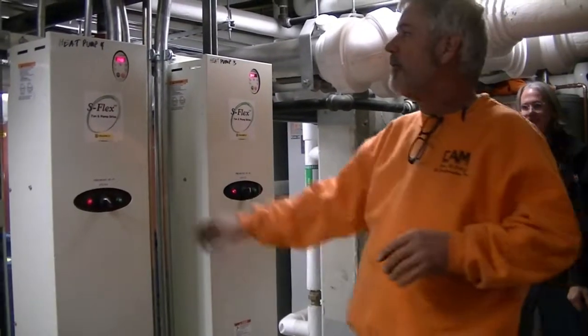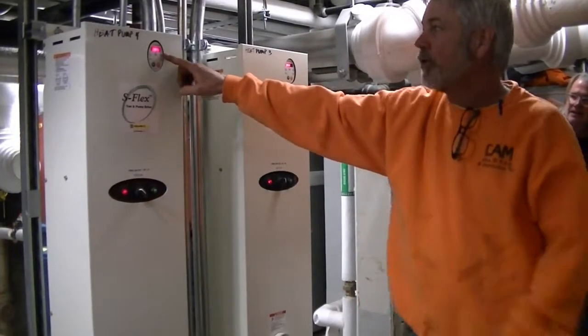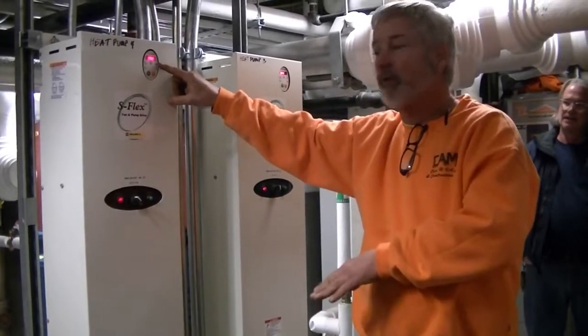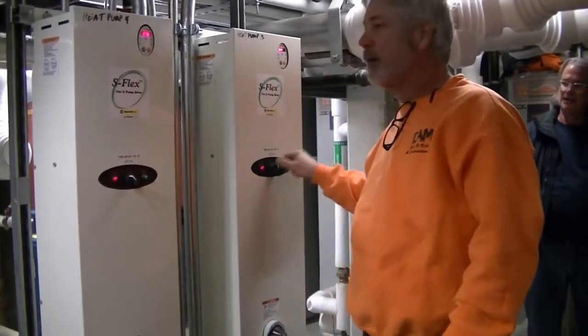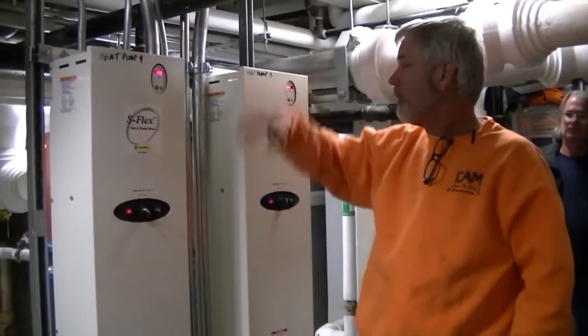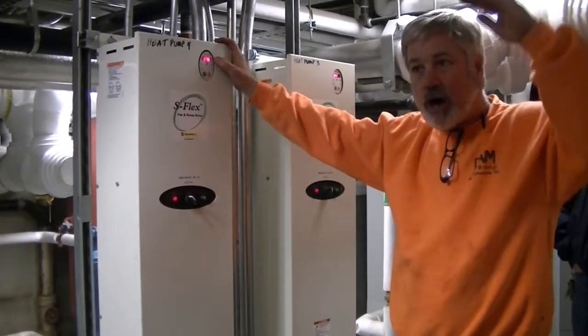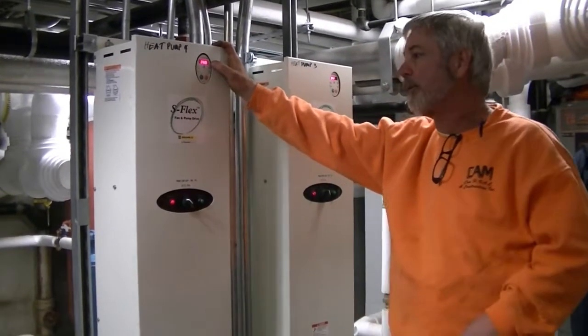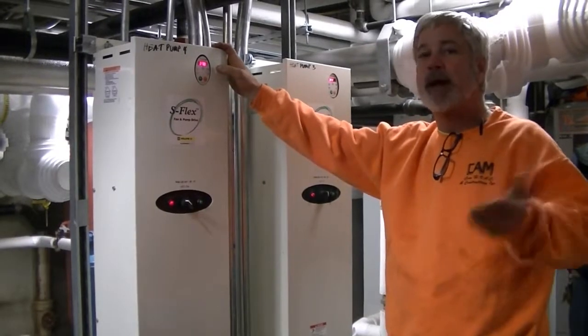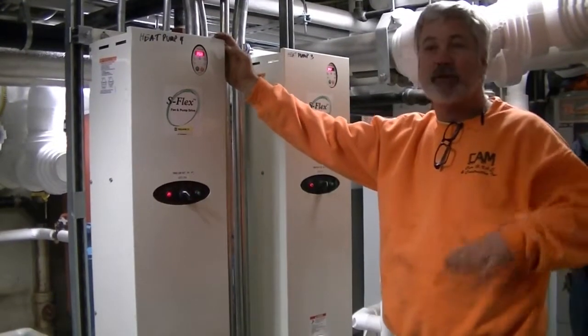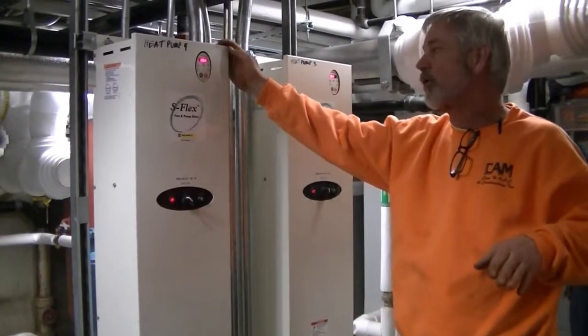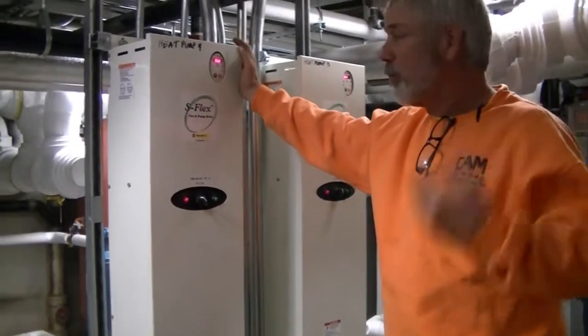Not a good idea. Now, if you just saw what I did, you heard the other motor start to slow down. It's because when I put this in bypass, I ran the differential way up. So what happened was the drive started compensating and shutting this drive down. When I turned it off, it came back up. Now it's going to hunt a little bit until it settles out. That's a normal occurrence.